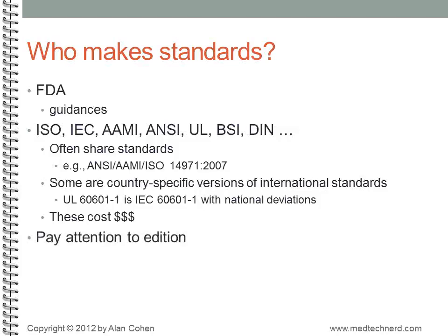Another important note is that you should always pay attention to the edition of a standard. Standards can be revised every few years, and once a revised standard is published, it can take years for different regulatory agencies to recognize the update. In some unhappy cases, different governments have recognized different editions of a standard for periods of time. Usually everyone catches up to the latest standard at some point, but be aware that the latest version may not be the one that you need to follow.